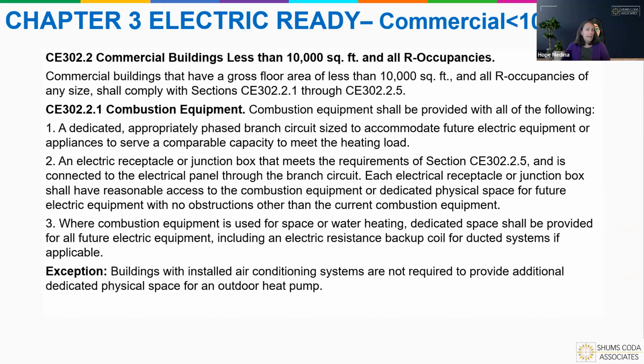It tells us we've got to have a dedicated branch circuit that's sized to accommodate future equipment or appliances and serve a comparable capacity to meet the heating load. So the idea is if we have this gas appliance here, and it's going to do 100,000 BTUs, we have electric equipment that could be swapped out to be installed in place of it, and it still meets that capacity. But when they talk about the capacity, it's not necessarily the capacity to heat the space. It's the capacity of the system that's involved to heat the space. And that's what they're looking at with this.